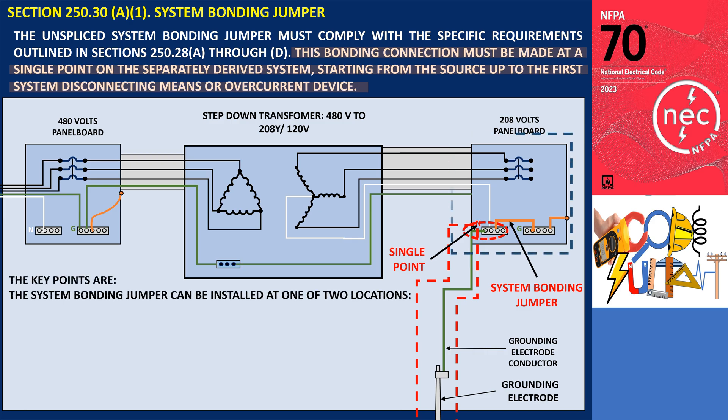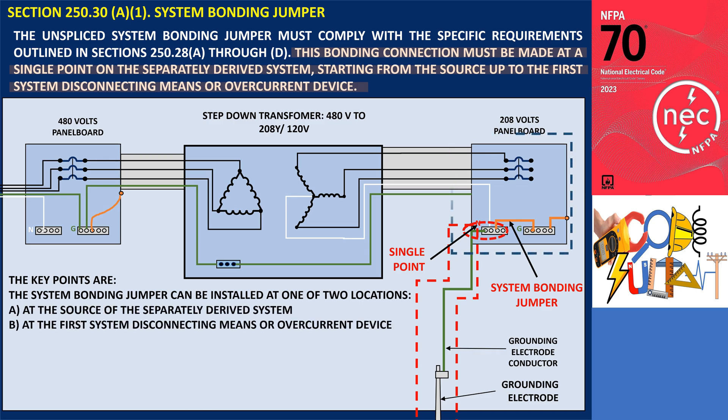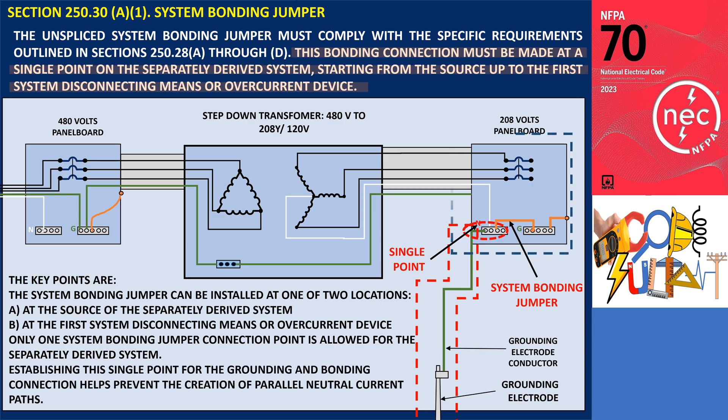Therefore, the system bonding jumper is required and permitted to be installed at only one location on the separately derived system, either at the source of the separately derived system, or at the first system disconnecting means or overcurrent device. This single point for the grounding and bonding connection is intended to reduce the likelihood of parallel paths for neutral current.